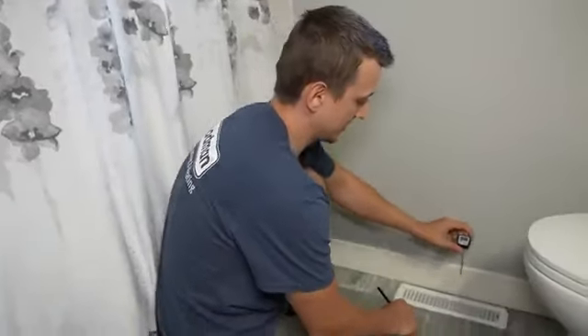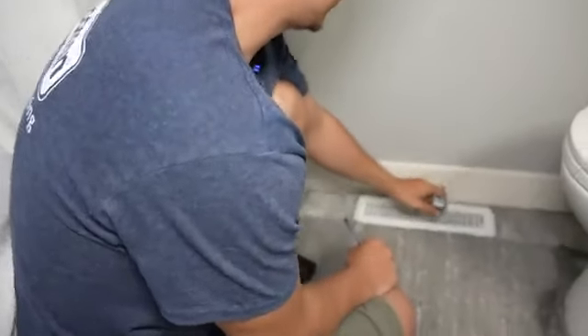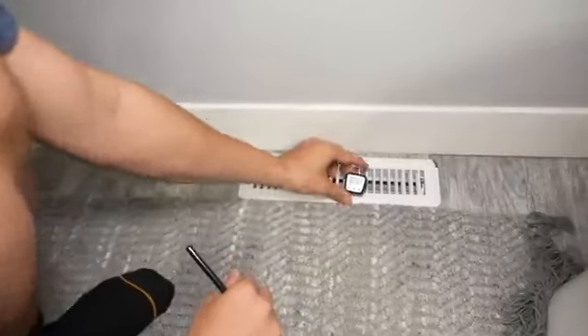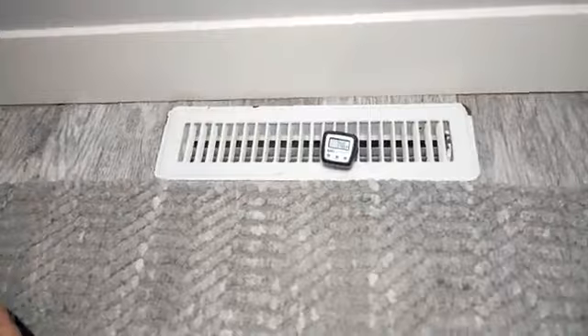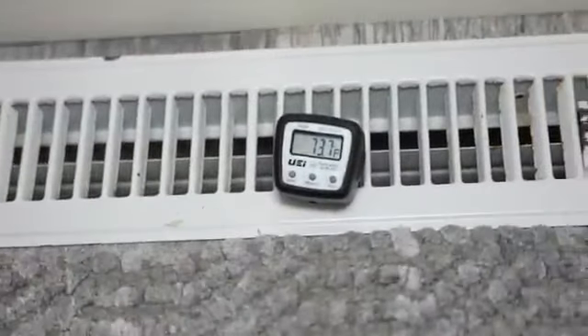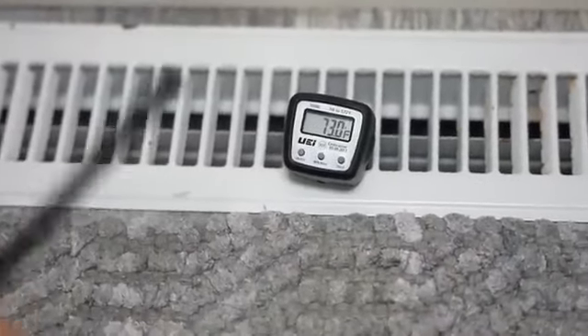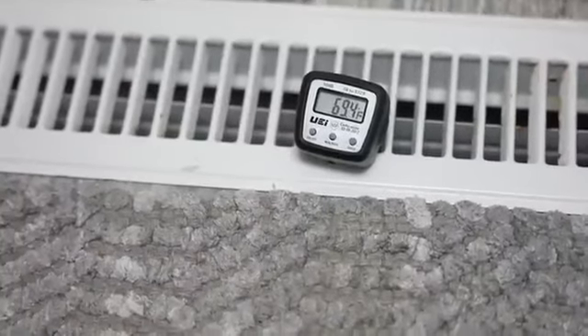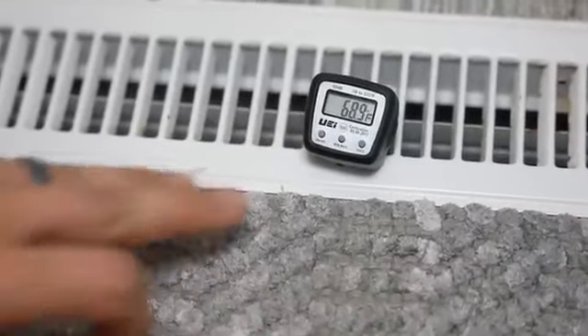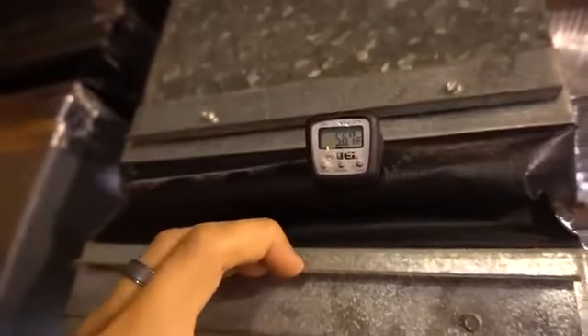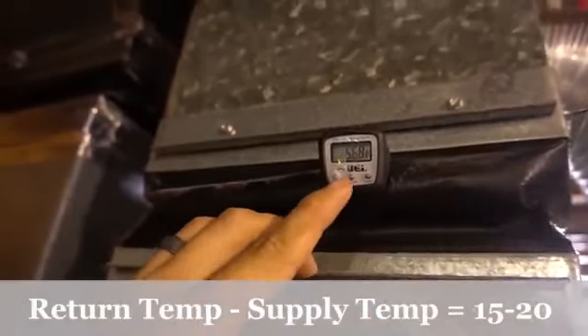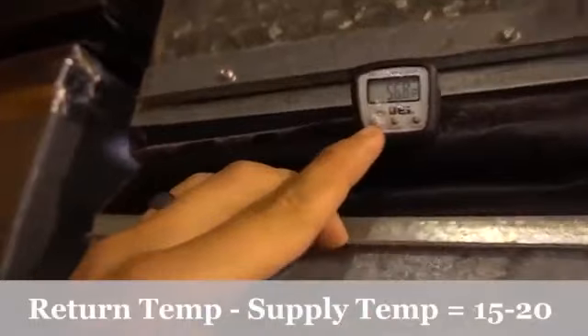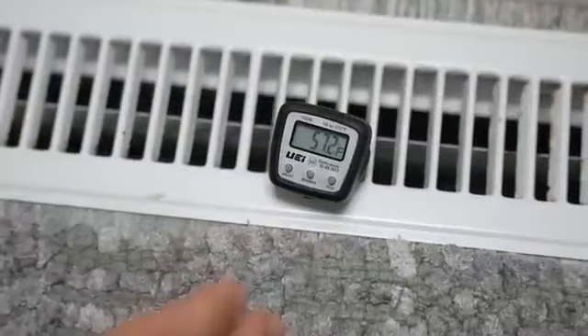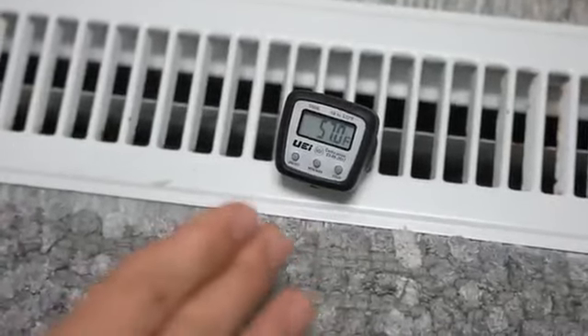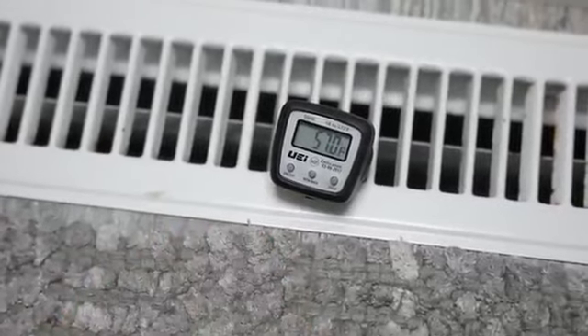Okay, so we found a vent in the bathroom. Let's see what kind of temperature we're going to get coming out of the supply. So our return was about 71 degrees. And our supply, we're gonna want at least 15 degrees lower. And by the way, I do have another video where I take a temp drop like this on a different furnace. So if you want another example, you can check that video out as well. I'll leave that in the description too. So we got to about 57 degrees and it really slowed down. It's going down really slowly.